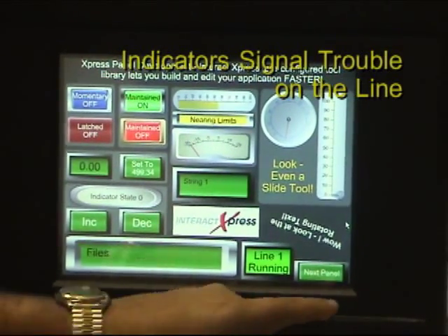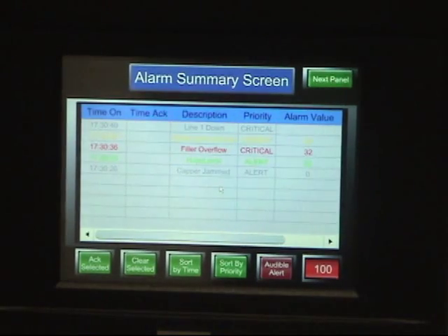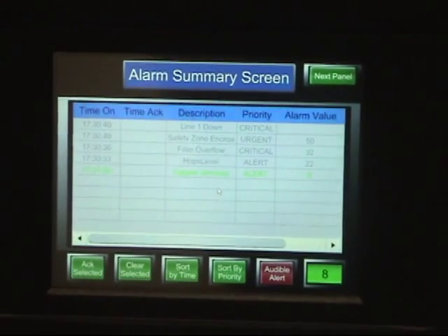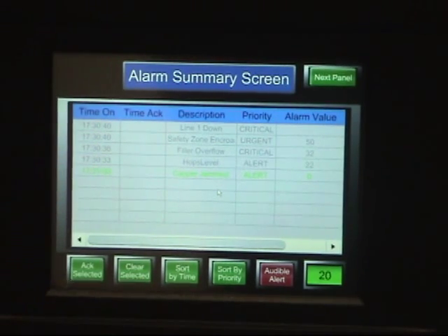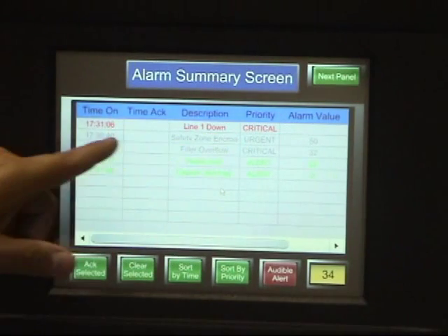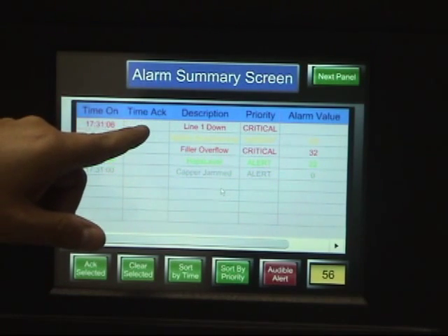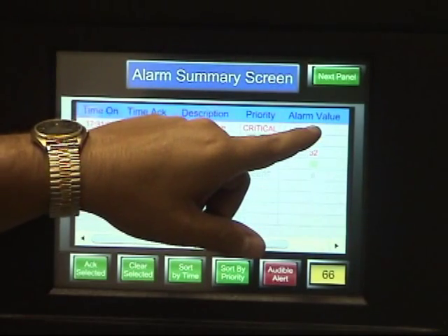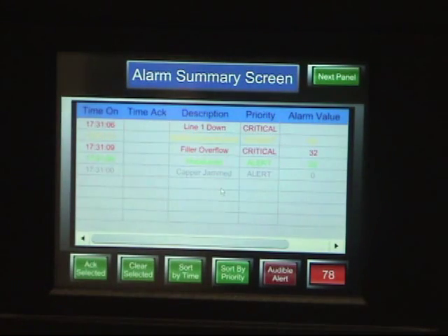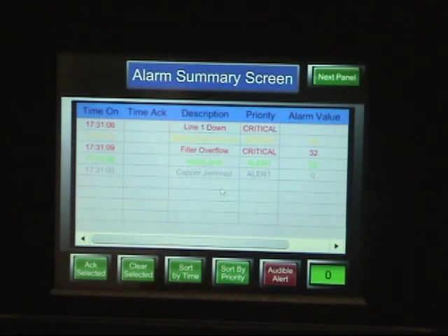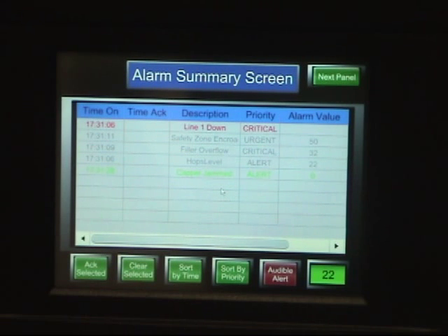In addition, if I go to another screen, I can actually log that data as it occurs on an alarm screen. We can see right now I've set up an alarm that says 'line one down.' It logs the time that the alarm occurred, the time that we acknowledge the alarm, a priority, and a particular value at the time that the alarm occurred. As the machine stops and starts, we're going to log that data every single time. Later I'll show you how we can retrieve that log file so we can do analysis on it and determine where there are critical problems in certain machines where we're having a lot of downtime.